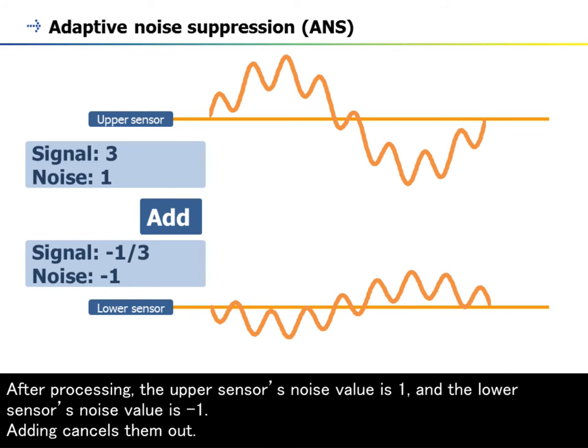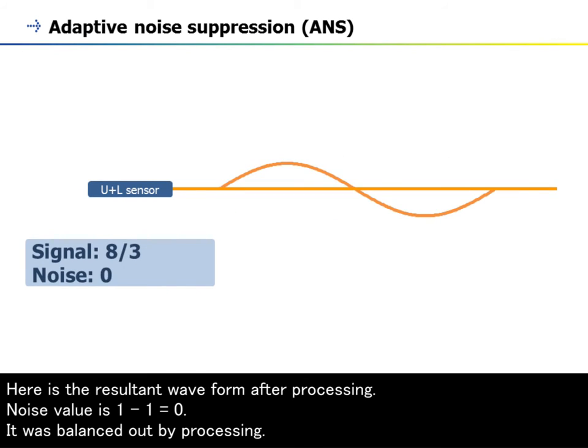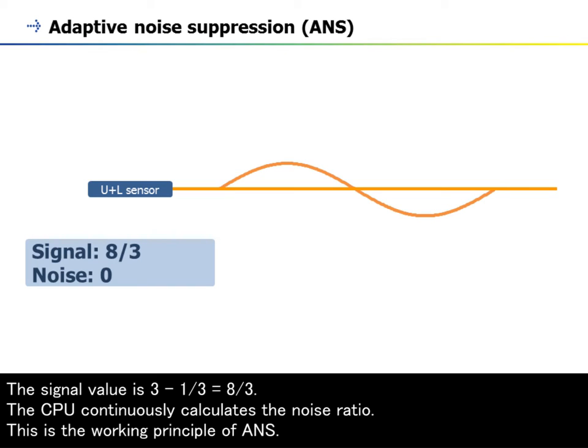After processing, the upper sensor's noise value is 1 and the lower sensor's noise value is minus 1. Adding cancels them out. Here is a waveform with the upper and lower sensor's output. Here is the resultant waveform after processing. Noise value is 1 minus 1 equals 0 — it was balanced out by processing. The signal value is 3 minus 1/3, equals 8/3. The CPU continuously calculates the noise ratio. This is the working principle of ANS.